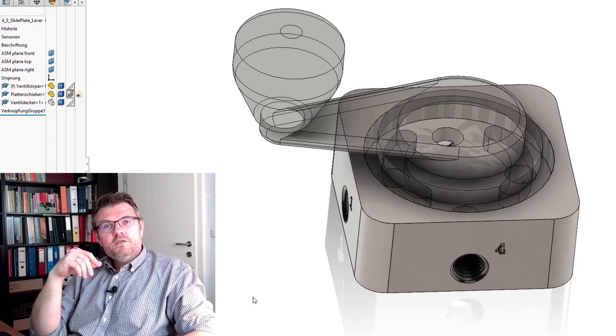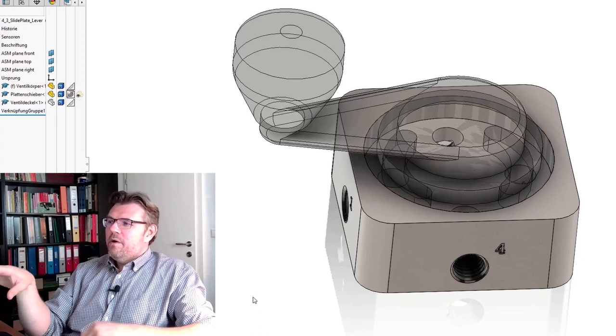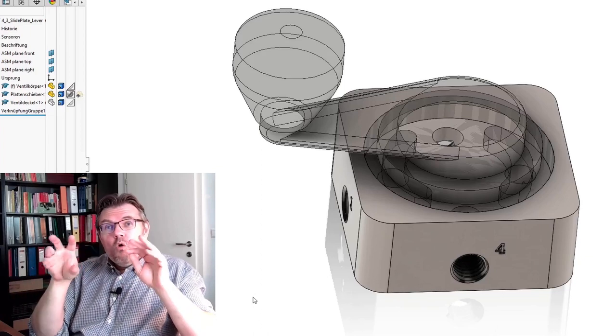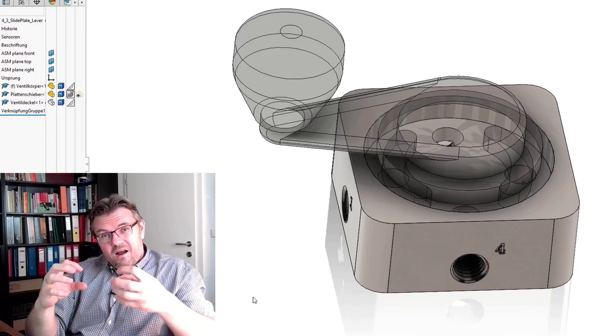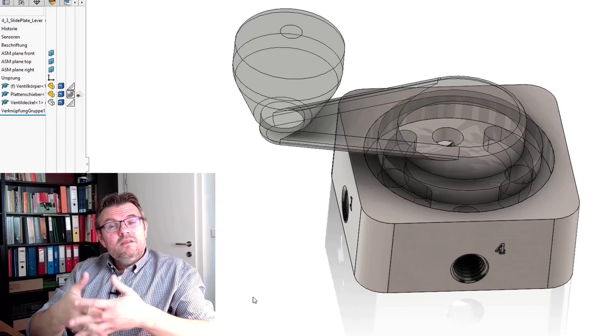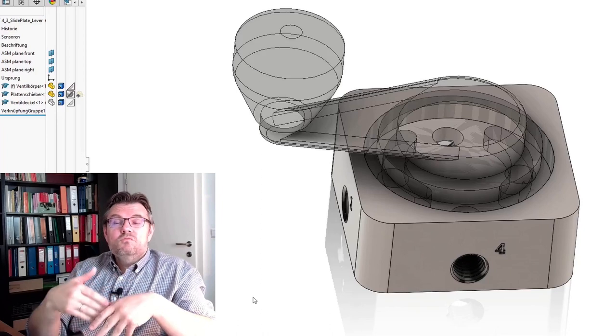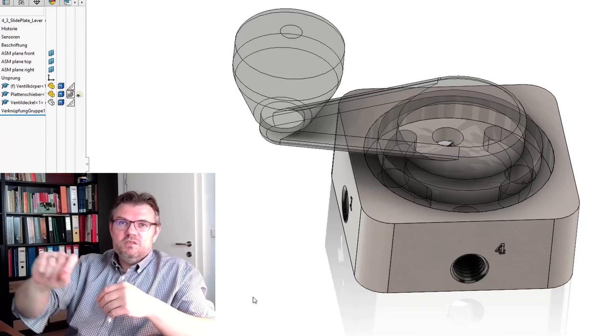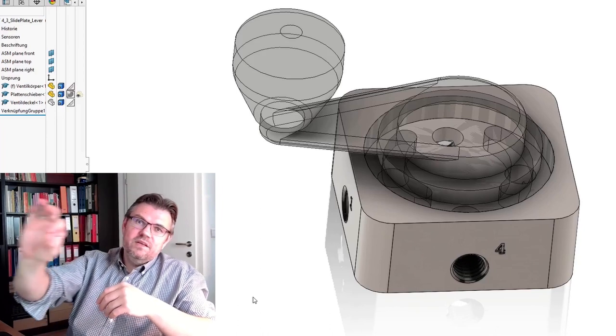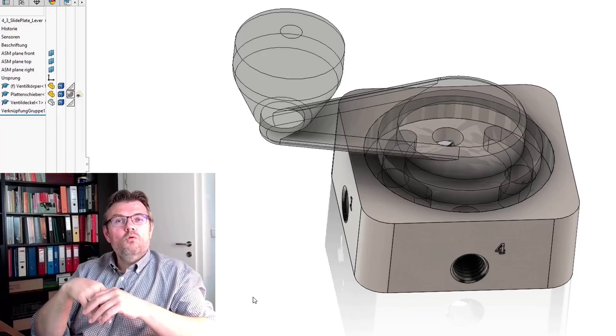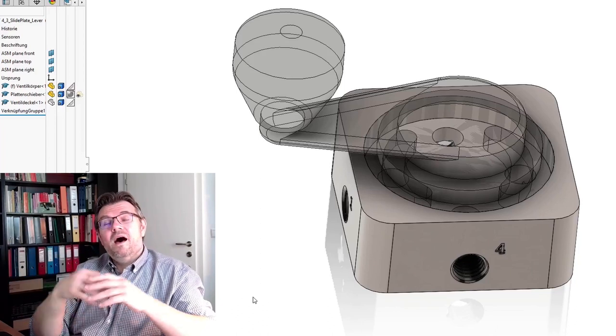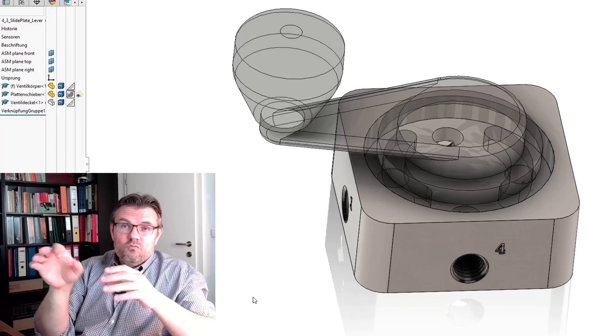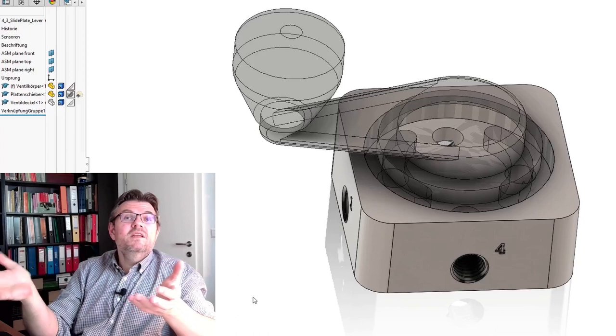There are also constructions out there where in middle positions, all connectors are interconnected to each other. This means the cylinder would be pressureless. This means I could move the cylinder easily. This would hold the cylinder, the other version would simply free the cylinder.